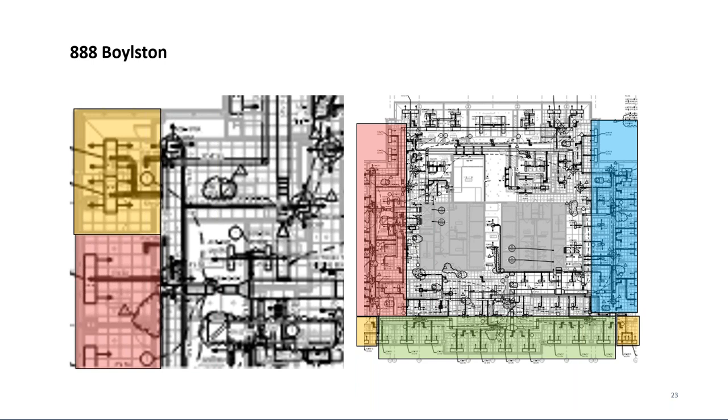A significant part to where we almost couldn't make chilled beams work, but with that shade pocket idea and with being able to boost up the flow to 0.35 CFM wherever you had a load, which was basically driven by solar, we were able to make that work.